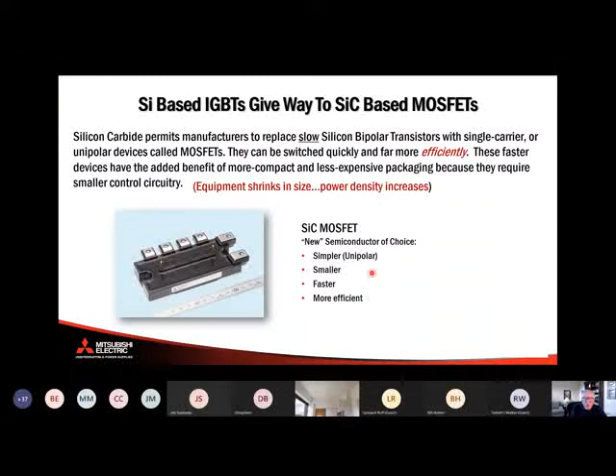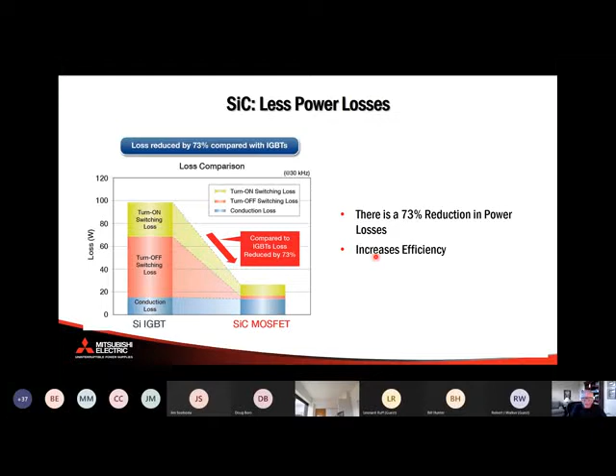So using silicon carbide in UPSs, we're going to see higher efficiencies, less heat rejection, less cooling, smaller footprint. Efficiencies using silicon instead of silicon carbide: on the left here, you have switching losses turning on the device, switching losses turning off the device, and conduction losses. Using silicon carbide, you're conducting for the same amount of time, so the conduction losses are the same, but switching it on and off, we're going to have a reduction in power losses by 73%. And you only need 1/10 the material. This is why these switching losses are so large, right?